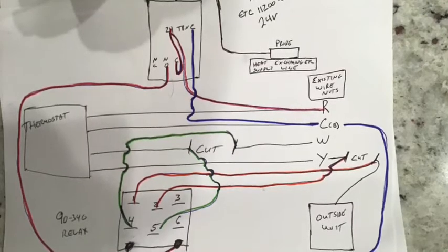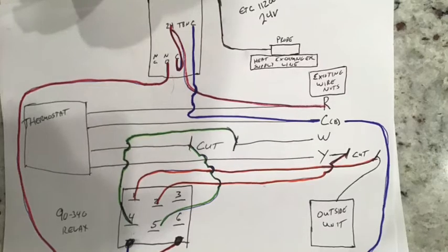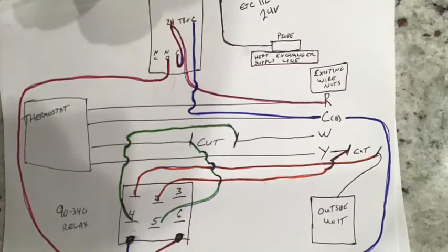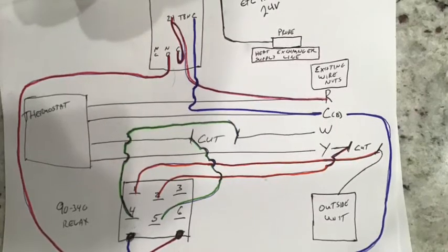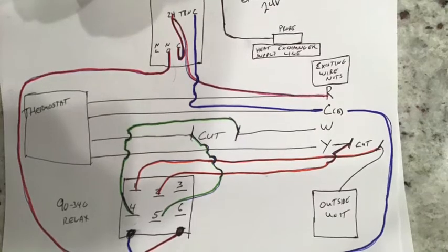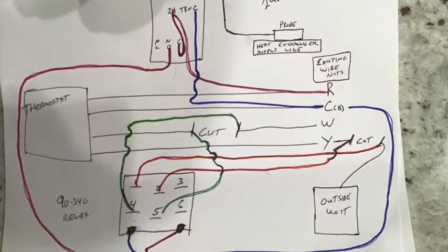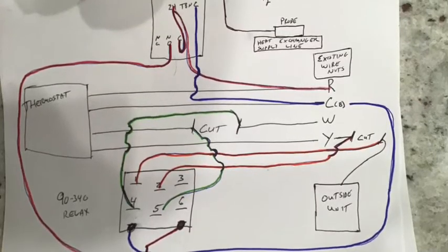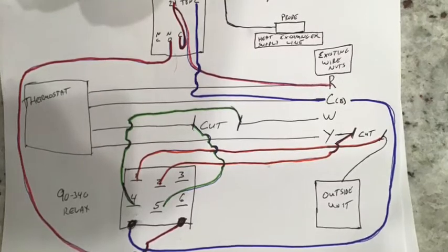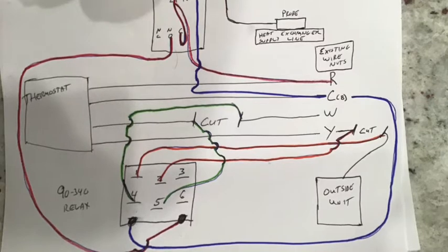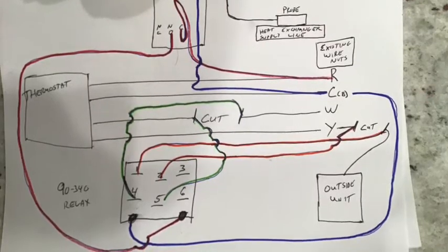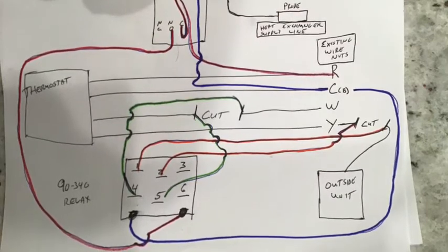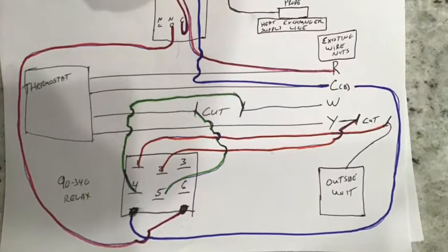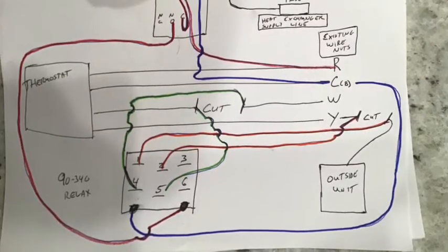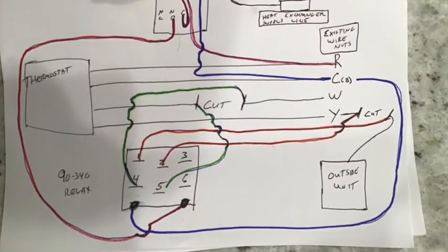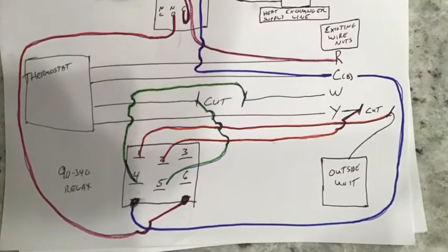So the reason you'd want to wire it up like this is to avoid having two thermostats. With two thermostats, you either have to turn on your thermostat to use your wood boiler, or you have to turn on your thermostat to use your heat pump. Wiring it up this way bypasses that. Anytime your thermostat calls for heat, it sends the signal to your air handler. The Aquastat will tell the air handler, yes, I have hot water, or no, I don't have hot water. If hot water is detected, the blower for the central air unit will turn on. However, the heat pump will remain off. If there's no hot water being supplied to the heat exchanger, then the heat pump and blower will turn on, creating your heat source electrically instead of through the heat exchanger.